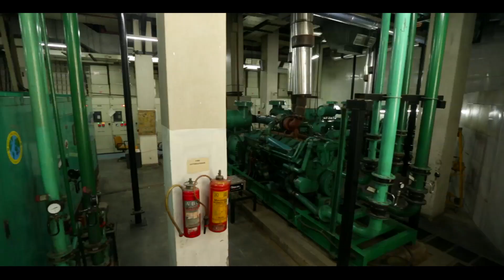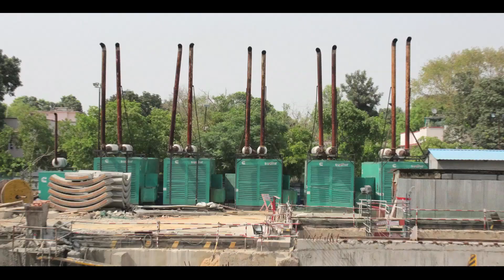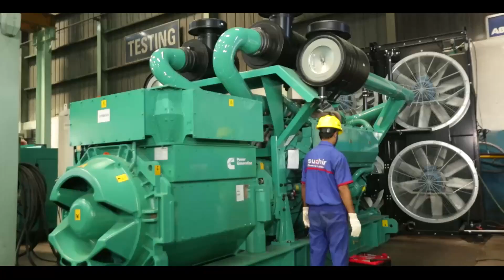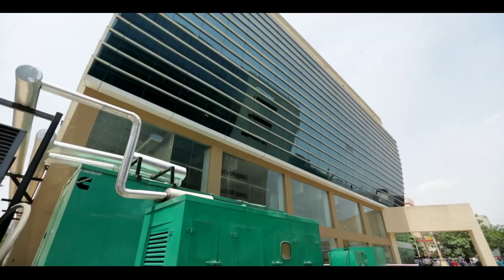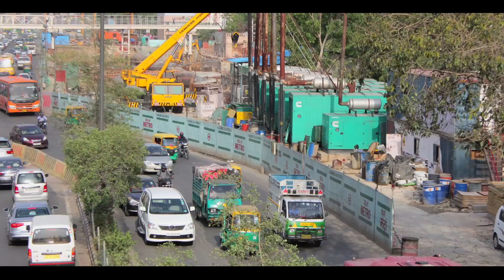Part 2 of the National Electric Code of India covers the requirements related to standby generating stations and captive substations. This part is divided into two sections. Section 1 is on electrical installation of standby generating stations, providing guidelines in respect of electrical design, selection along with installation, testing, commissioning, maintenance and statutory compliances for standby generating sets having individual capacity up to and including 2000 kVA.